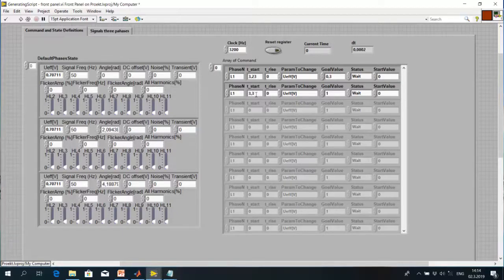It is important that the disturbance should not last longer than 200 milliseconds. There are definitions in the European standard that I have mentioned before for each disturbance, but here for the sag and for the swell, it is important to not last more than 200 milliseconds.